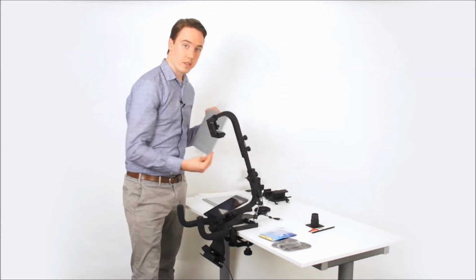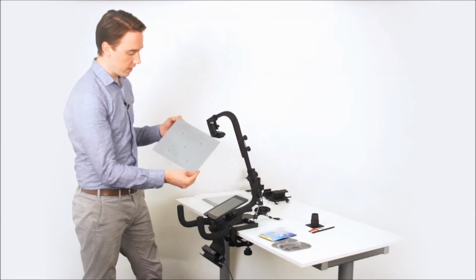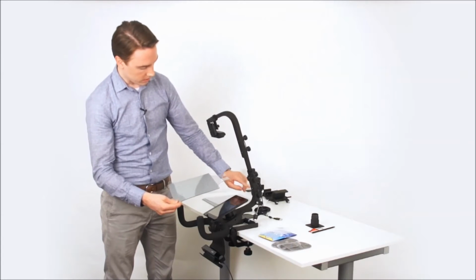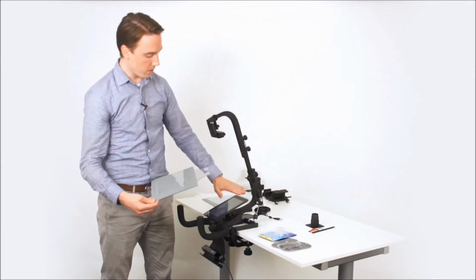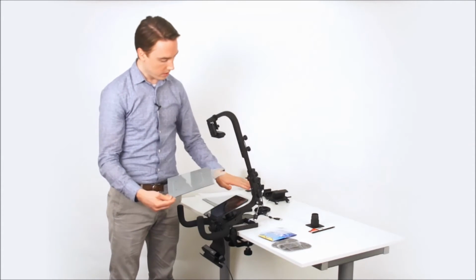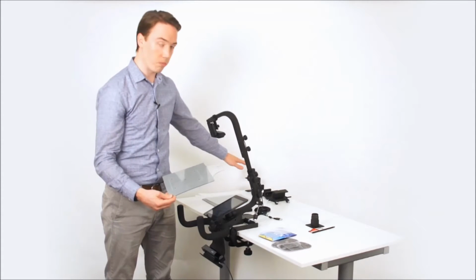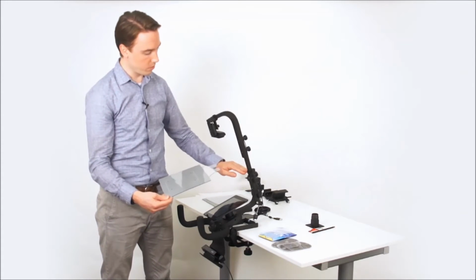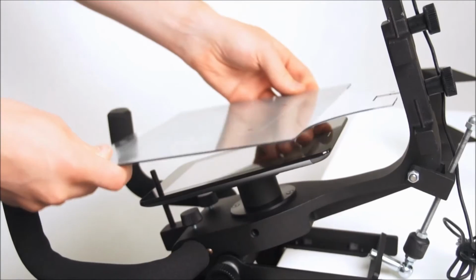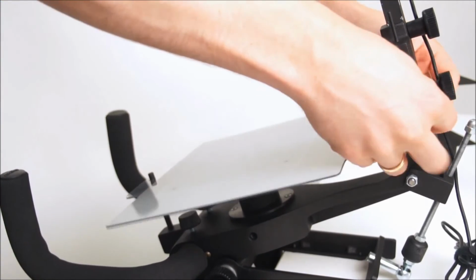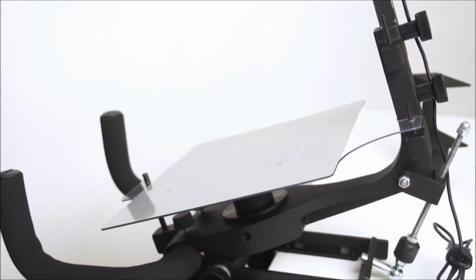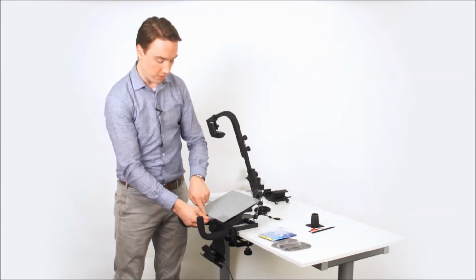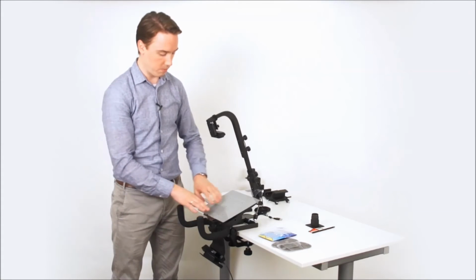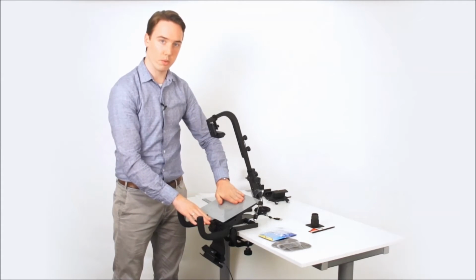The next step is mounting the calibration board. The calibration board slides over these pins. When you're using the flat mount, it slides over the lower pins. If you're using the bracket mount, it will slide over the top pins. So just align the holes in the back and slide it down, and align the hole in the front with the fixing rod, just to make sure it stays in place. It should be flat on the mobile device.